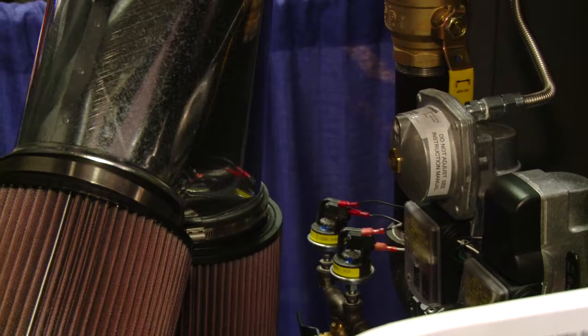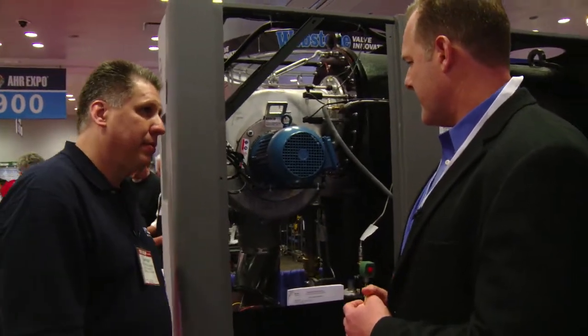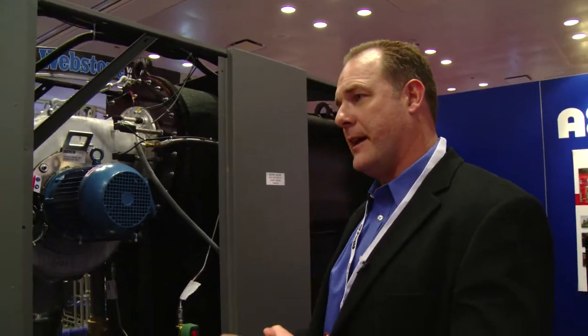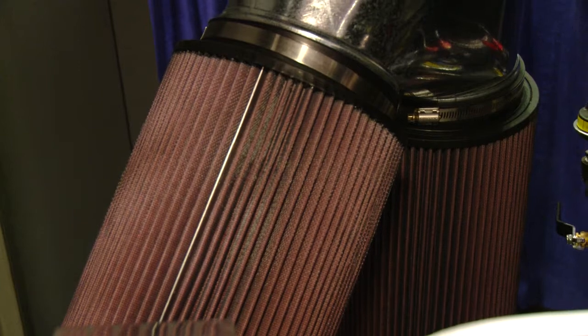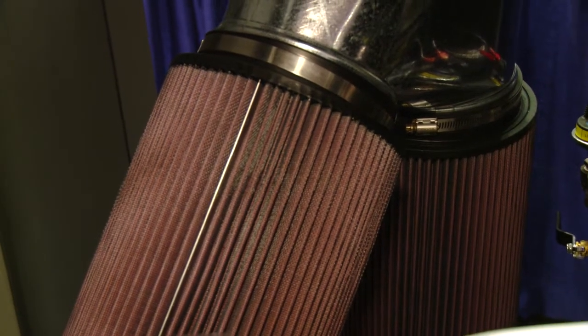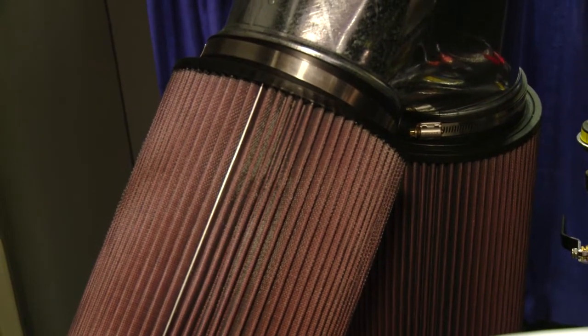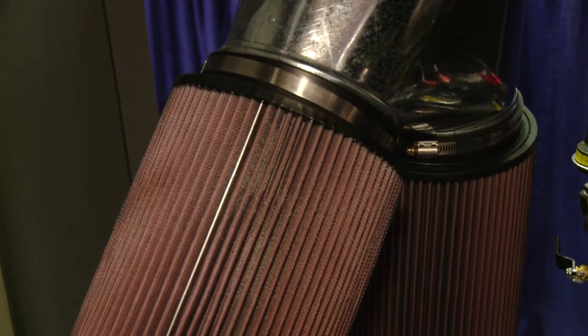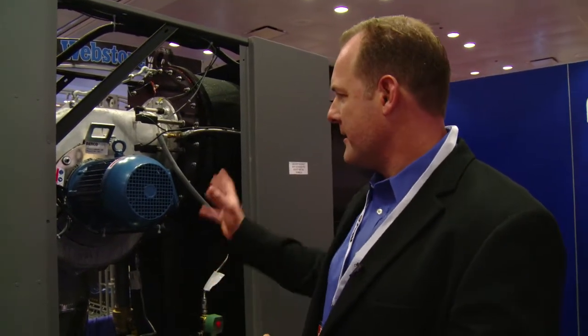I see that you filter your incoming air, your combustion air. That's a unique feature of this boiler. Yeah, that is unique. One thing about when you're dealing with combustion products, it's very important to have a good airstream and proper air fuel, air and gas delivery to the burner. And putting K&N air filters on the incoming airstream certainly guarantees that we're not going to bring in any mechanical room debris, which we all know how clean mechanical rooms are today, but it really ensures the proper combustion downstream in our burner.